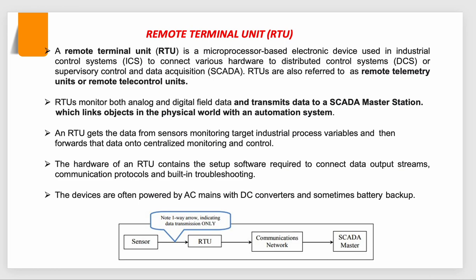The RTU will collect data from machinery and transfer that data to the SCADA — Supervisory Control and Data Acquisition — which we already discussed in the last class. The RTU collects data by the help of sensors from machines, pumps, and motors. Sensors tell us whether the machine is working or not, whether the pump is on or off, and whether pressure in the pipeline is high or low. The sensor gives data to the RTU, and the RTU transfers this data from the remote location to the master station, to the SCADA.